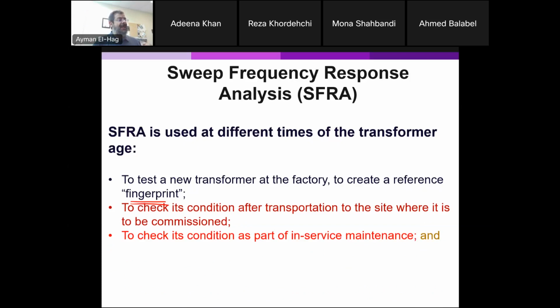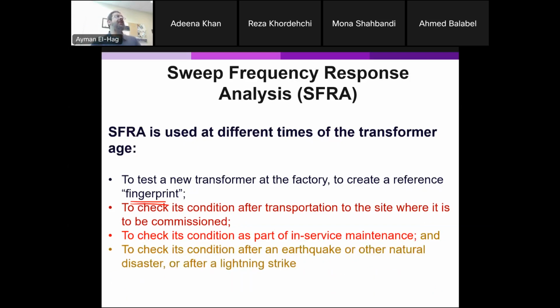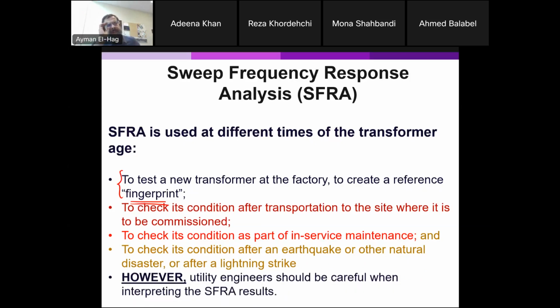Also, you can check the transformer in service. If a fault happens inside the transformer, you start to have a short circuit within the windings. If you start to have a deformation in the windings, all of this can be detected in service using the SFRA. And finally, if an earthquake happens in a certain region and you want to see if something happened internally to the transformer. But this always relies on the fact that you have to have a fingerprint. Sometimes, if you have a similar unit, you might use it as a fingerprint if you don't have any other fingerprint for the actual transformer. However, with this test you have to be very, very careful when interpreting the data, because you can easily misread the data and come up with a wrong conclusion.